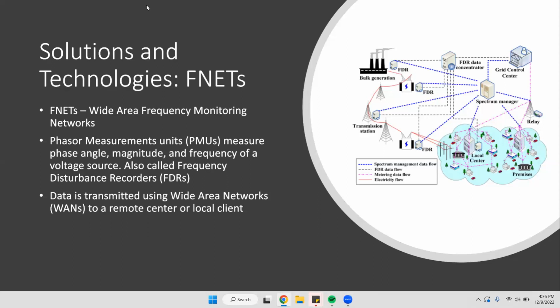As you can see on the diagram on the right hand side, there are FDRs or measurement units at each of the important nodes of a power system. So you can see that at bulk generation, there's an FDR at the transformer that steps it up, or the substation transformer that connects generation to transmission. You have another one at the distribution sub, and one at the transmission sub. So all of these are recording the phasor measurements of the feeders and the lines and generation - recording the voltage source magnitude, phase, and frequency of the system.